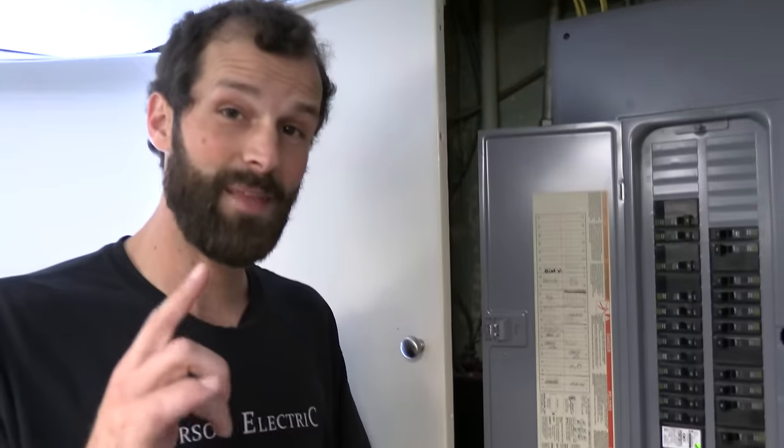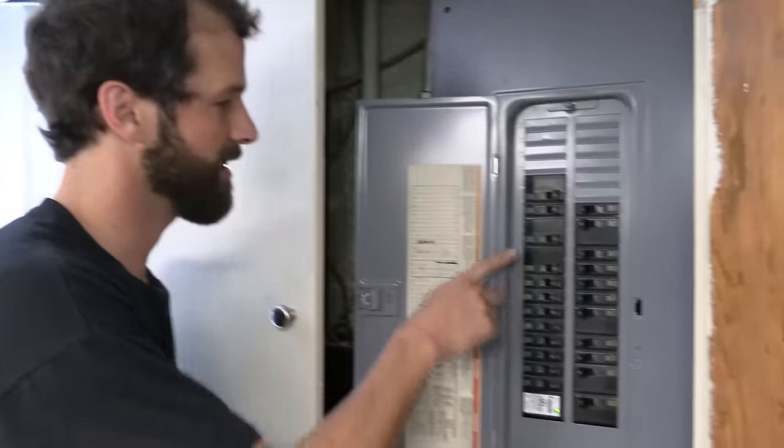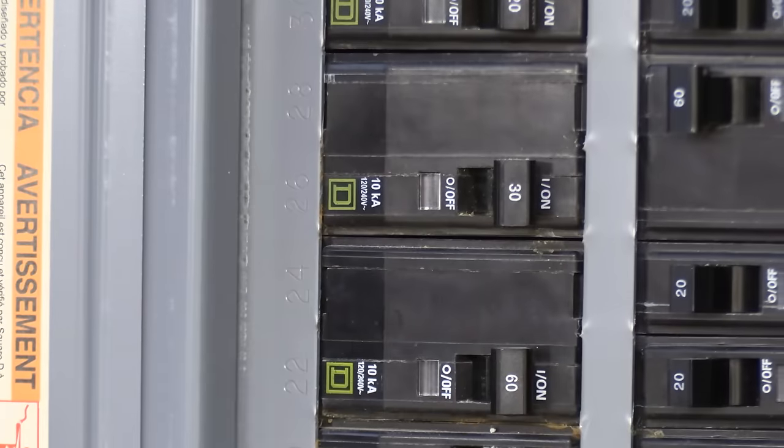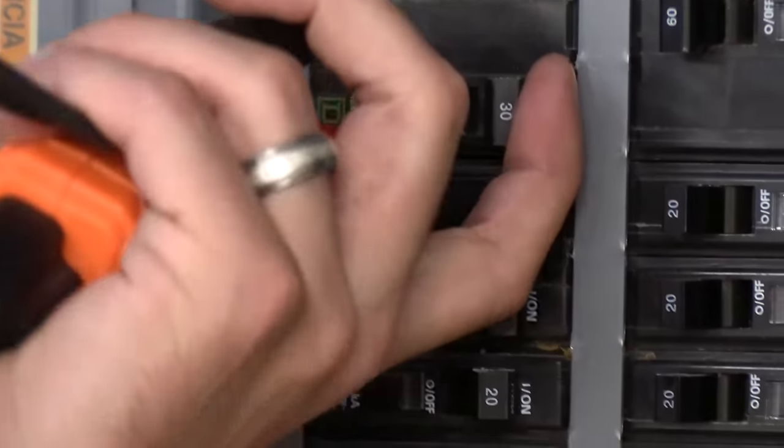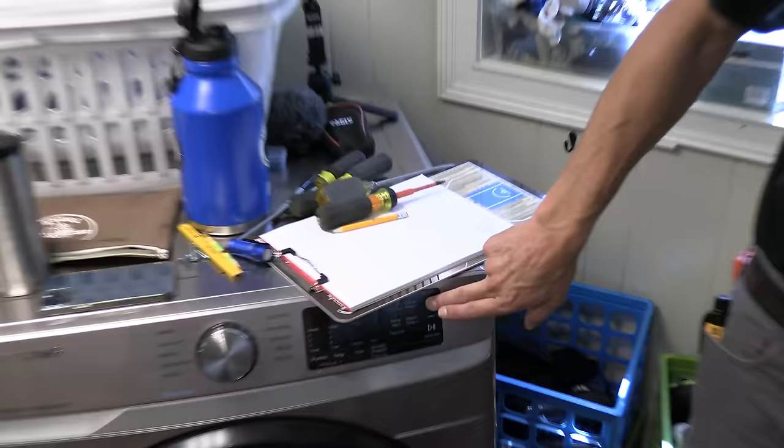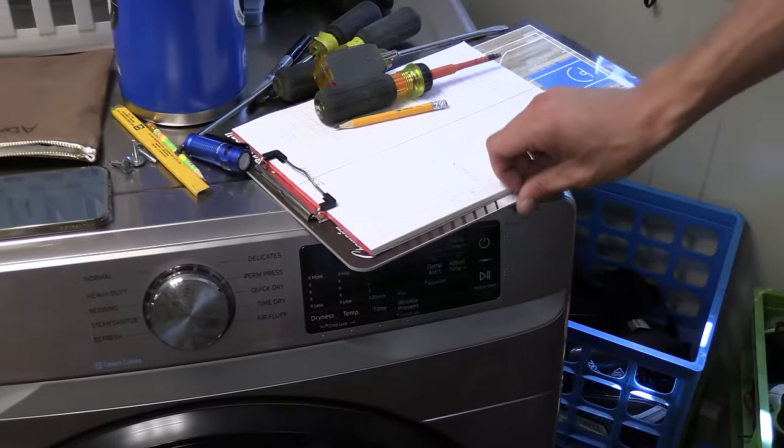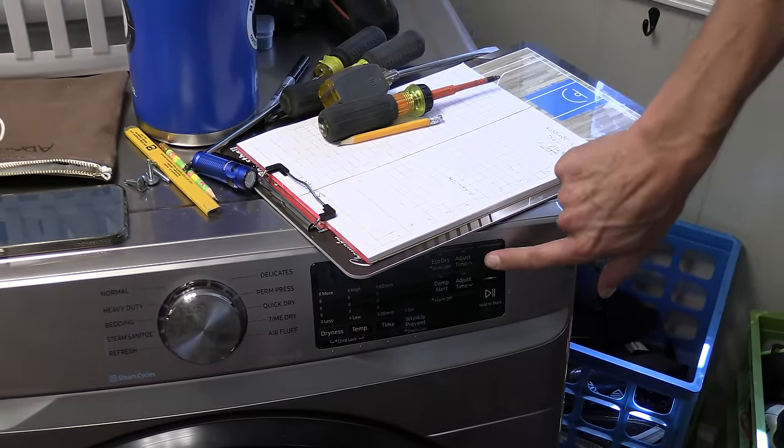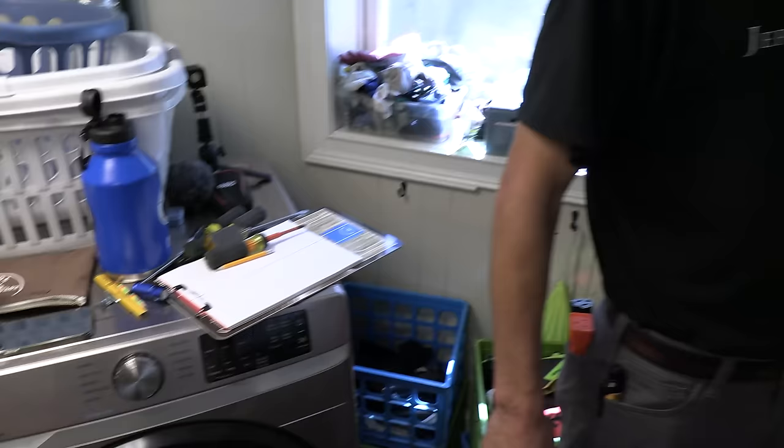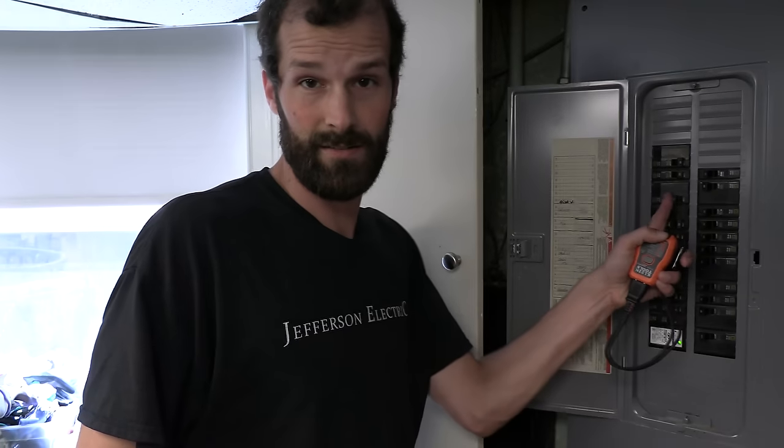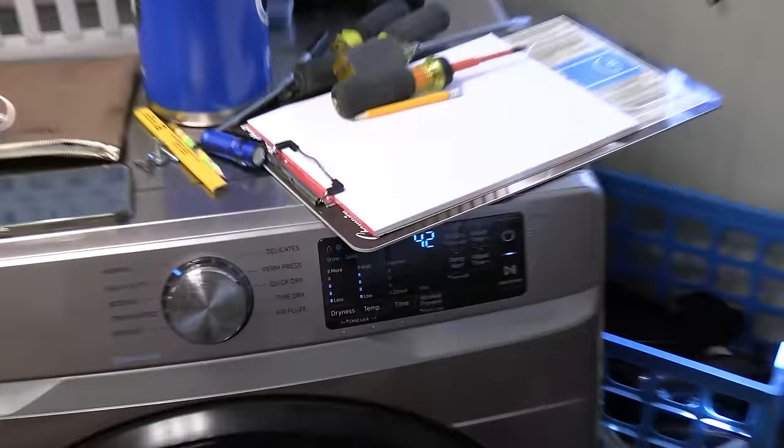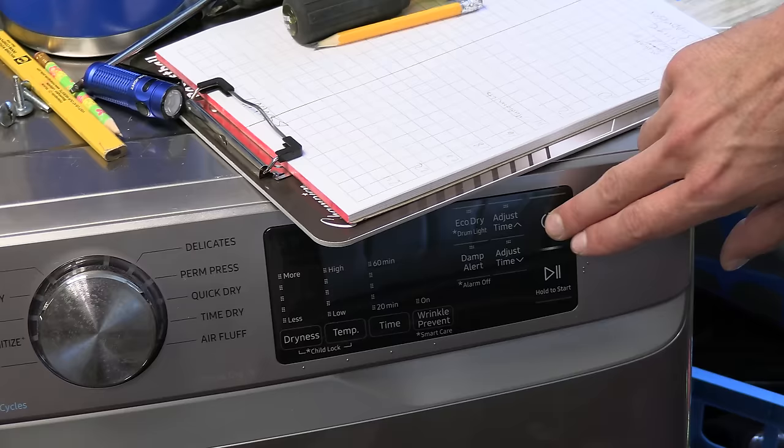The last item that we have to determine in the mudroom is the dryer. An electric dryer is almost always on a two pole 30 amp breaker. So I'm going to leave it in the off position. I'm going to flip my breaker off, and then I'm going to attempt turning it on. And I think that's a gentler method as opposed to turning it on and flipping it off. So now the dryer has become unresponsive. I'm going to reset the breaker to the on position, and I expect, yeah, that's an easy one. Confirmed.